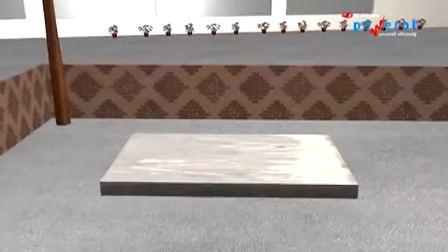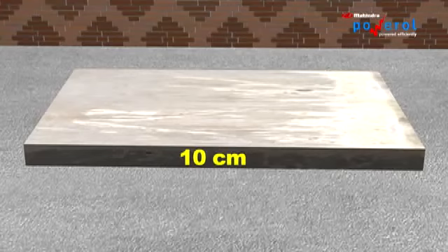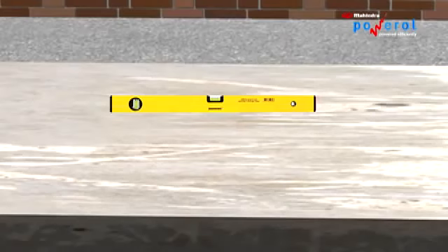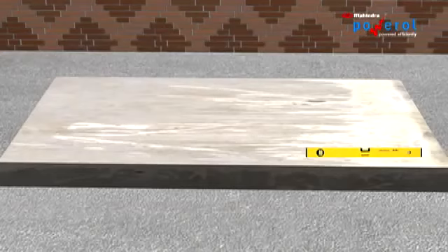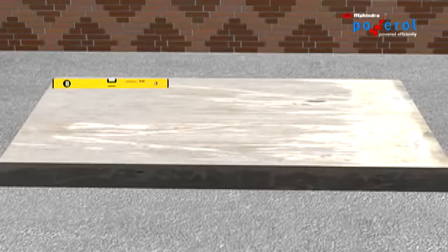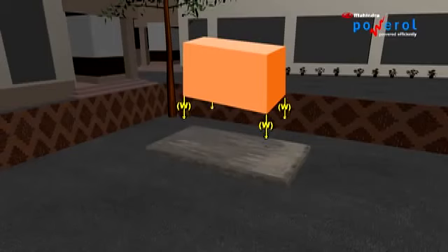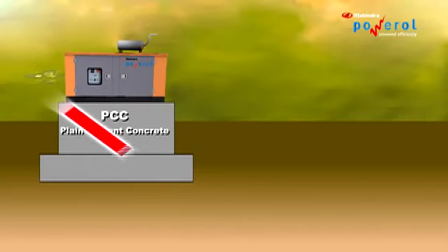Concrete block should be 10 cm above the ground to maintain cleanliness. Surface of concrete block should be at one water level. Use a spirit level to measure the flatness of the concrete block surface. Note: the pressure applied by the dead weight of the genset must be lower than the load bearing capacity of the foundation. A bad foundation will lead to excessive vibration, resulting in various failures in the genset.